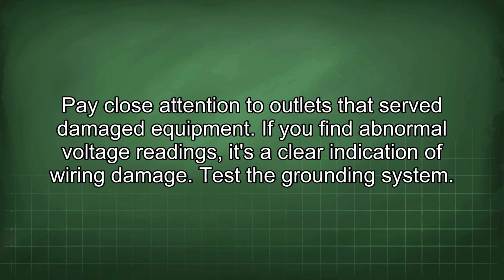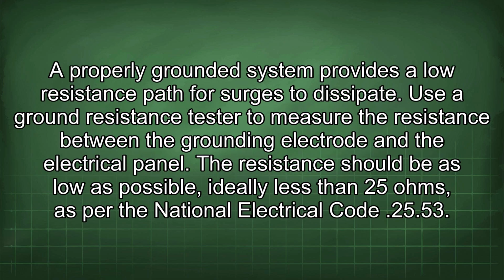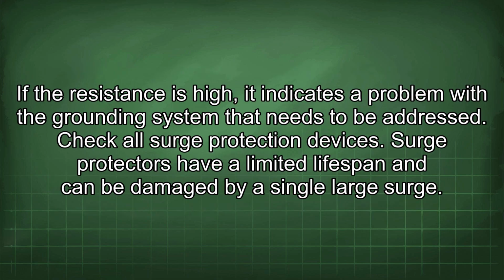Test the grounding system. A properly grounded system provides a low resistance path for surges to dissipate. Use a ground resistance tester to measure the resistance between the grounding electrode and the electrical panel. The resistance should be as low as possible, ideally less than 25 ohms, as per the National Electrical Code 250.53. If the resistance is high, it indicates a problem with the grounding system that needs to be addressed.